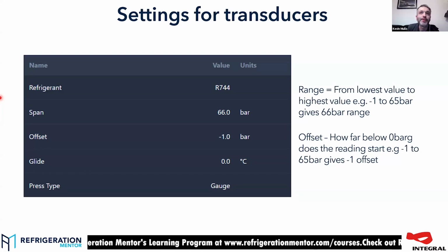So if you don't use the glide, depending on how the controller is, you will either end up with a temperature that's at the bubble point for your superheat calculation, which is not going to sit well with you for the actual superheat at the outlet, or if you push the glide too far, you're going to end up with it at the dew point, which can give you starving of the coil.